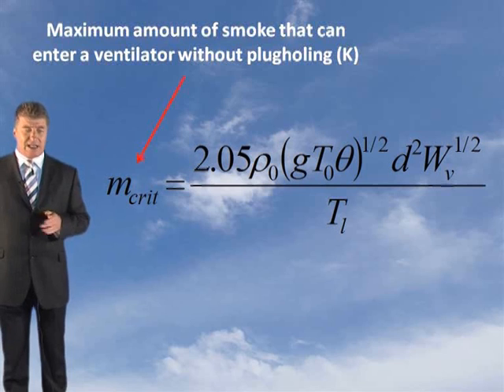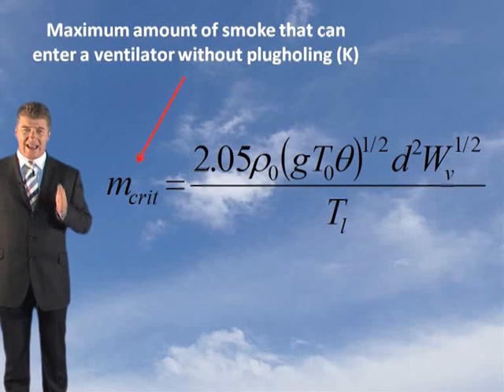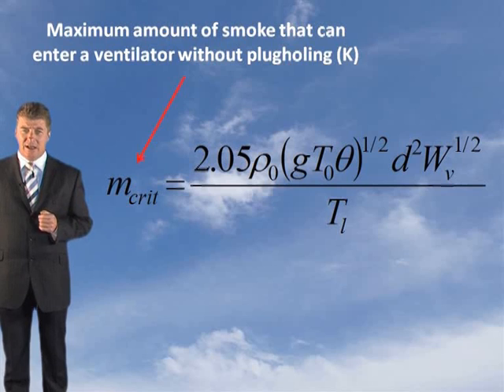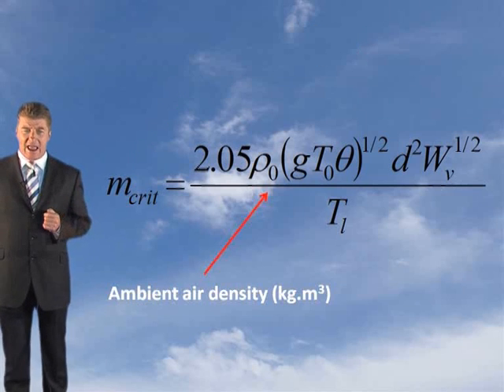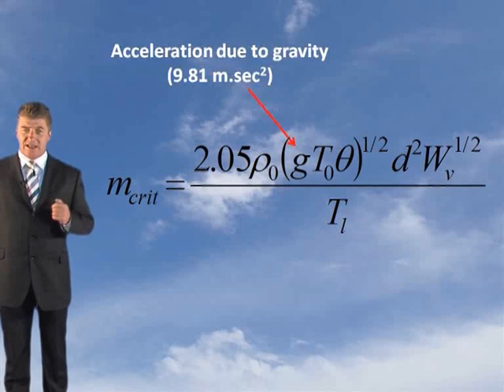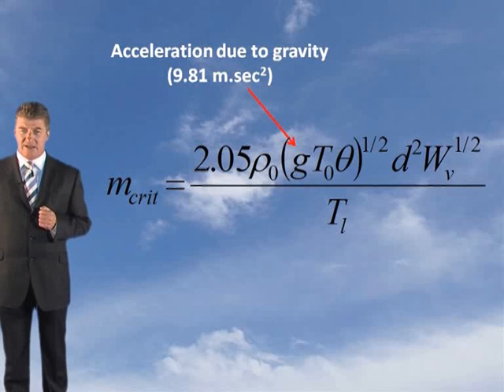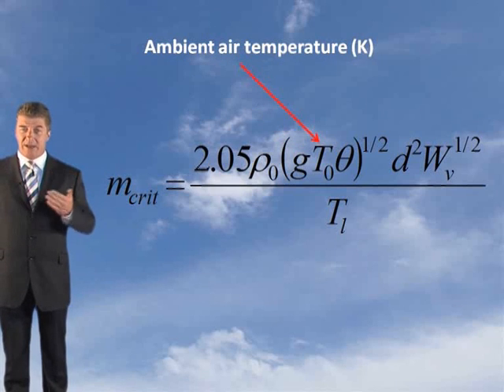Where MCRIT is the maximum amount of smoke that can enter a ventilator without plug-holing occurring, your ρ₀ is your ambient air density, you've got your gravity, 9.81 metres per second squared, you've got T₀ which is your ambient air temperature.